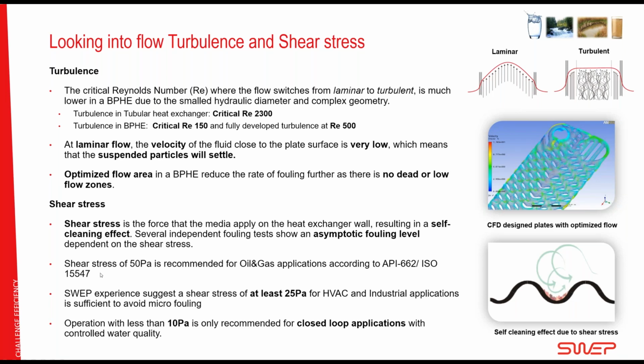Shear stress is well known as an important factor, and if I go to API 662, American Petroleum Institute, and it is also available in the ISO 15547. This is for recommendations for working in the oil and gas applications. So for plate heat exchangers in oil and gas, a 50 pascals shear stress is recommended. SWEP has found that this is good. More shear stress is always good, but we suggest that even 25 pascals is also a good value working in HVAC and industrial applications, even if the water is not perfect.